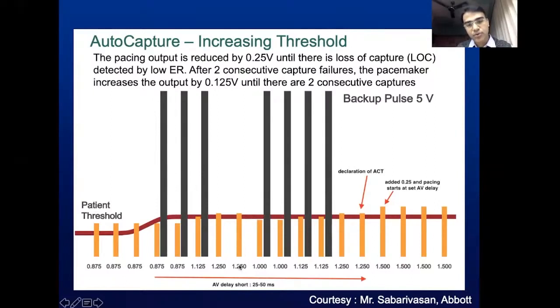How does it do this? It comes down by 0.25 volt. Like in this case, let's say the capture was found at 1.25. Now it will start auto capture threshold testing. It will come down by 0.25. It paces at 1 volt, but there was no capture. So no significant evoked response was detected. Hence, there is a backup pulse. This happens twice. So it goes up by 0.125 volt. And let's say that also there is no capture. So it gives a backup pulse. After that, it again increases by 0.125. And let's assume that at 1.25, there is an appropriate capture. So after 2 appropriate captures, the device declares that this is my auto capture threshold.